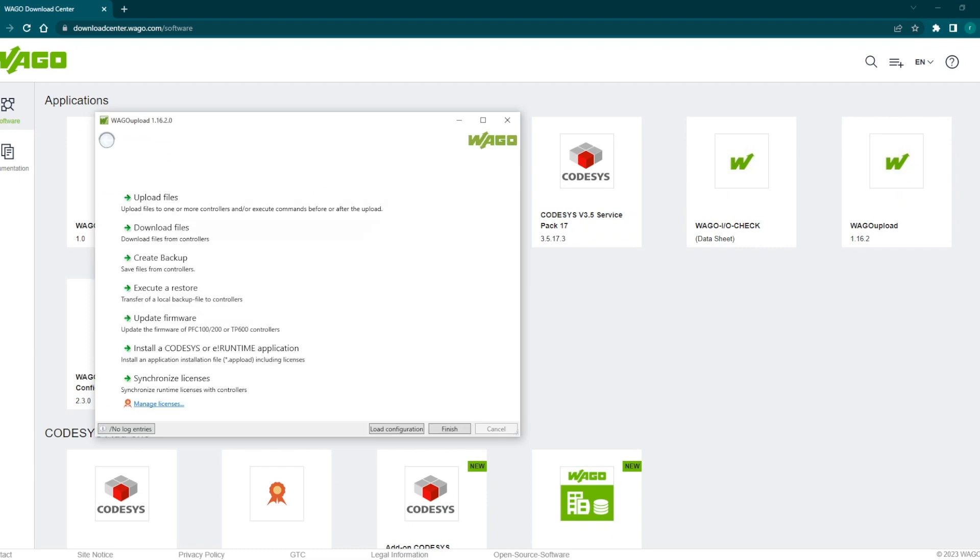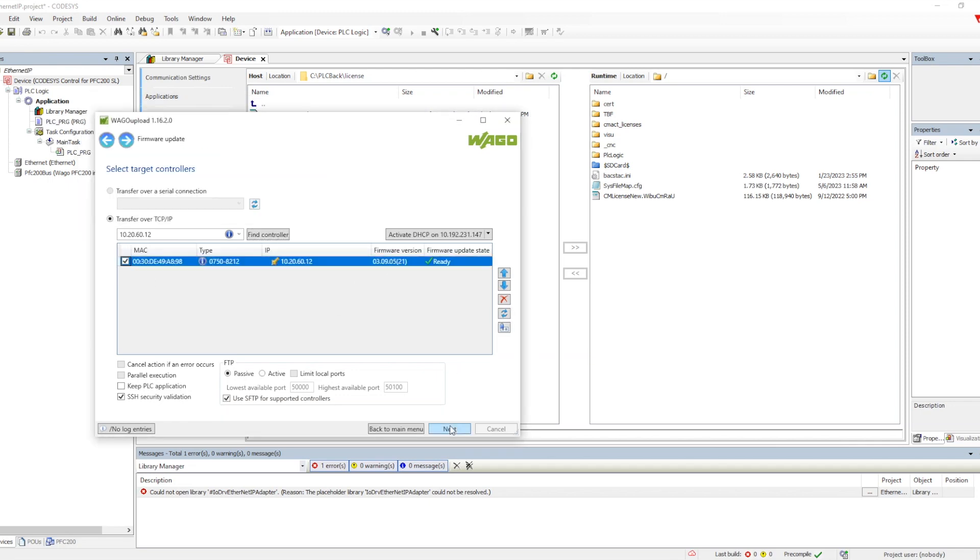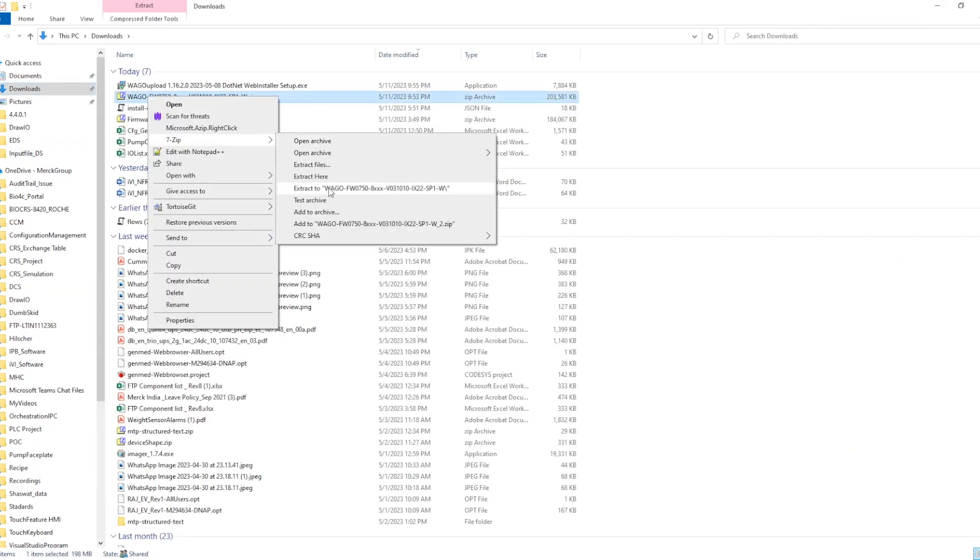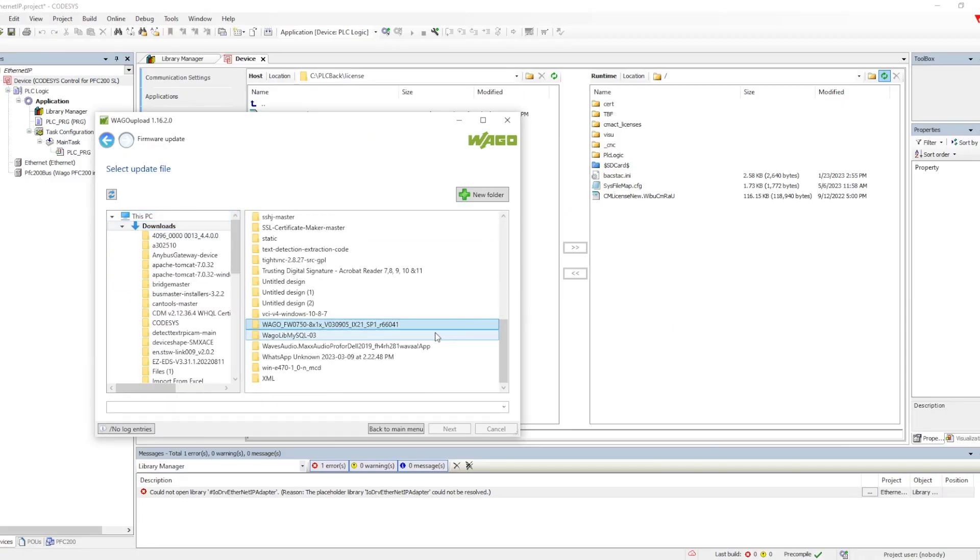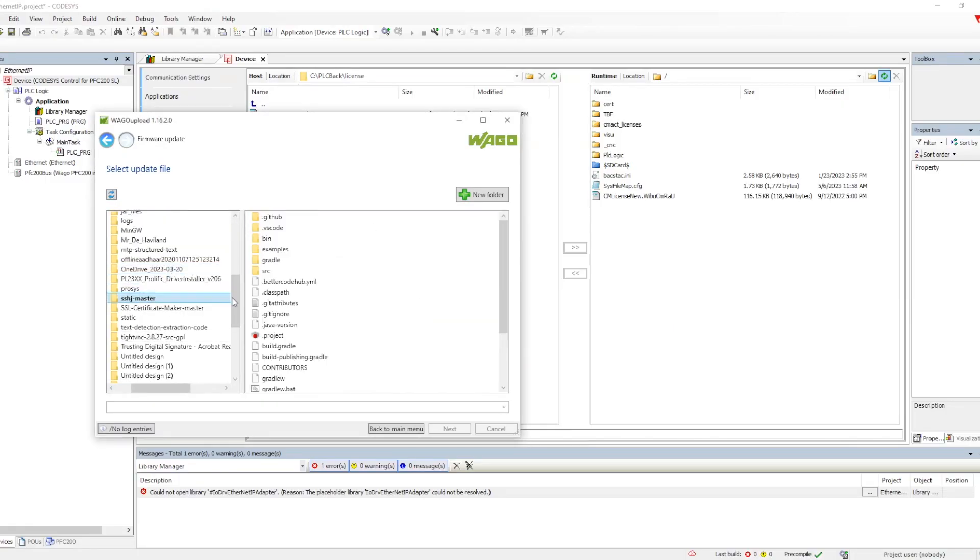I am utilizing the WAGO upload software to update the firmware. This particular software is also there in the download center which we can download. Earlier if you remember we used to do the firmware upgrade using memory card and putting that into the PLC, but this has been made easy using this particular software. We need to provide the IP address of the PLC, connect it, and then select the firmware.